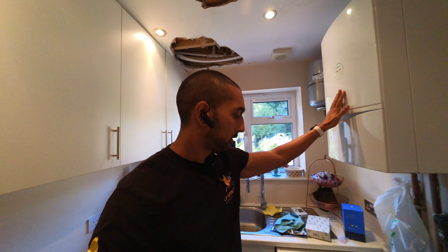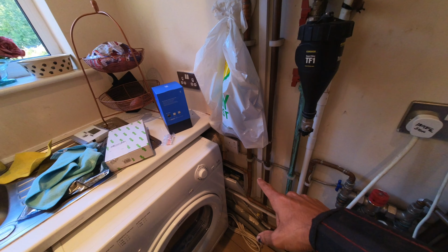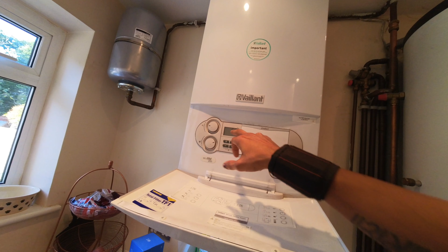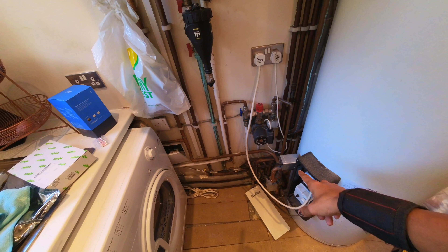Right, so this next job I've got here is a Vaillant 637. Previously it was on the old style Vaillant sensor comfort system or whatever it used to be called, which stopped working - I had a call saying there was no hot water last week. Originally I thought it might be a zone valve issue, but when I came here it's just not working properly. The PCB on here also needs changing because the temperature numbers just keep jumping about all over the place.